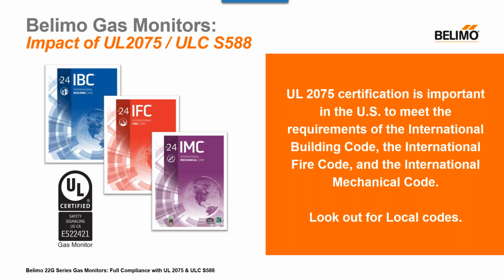By installing UL certified monitors, facility managers can ensure compliance with these codes, thereby avoiding potential fines or legal issues related to non-compliance. One should always also be aware of requests from insurance providers and also be aware of local state codes. Some authorities and their inspectors are known for strict enforcement beyond electrical codes, and they may require the installed CO detectors, sensors, transmitters, and controllers to be UL listed.